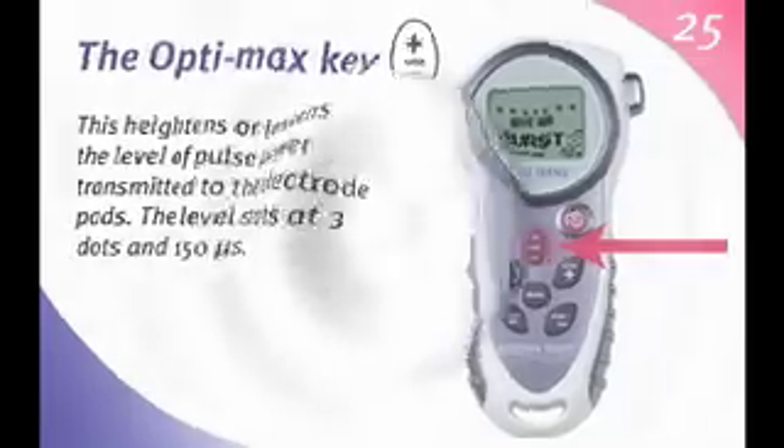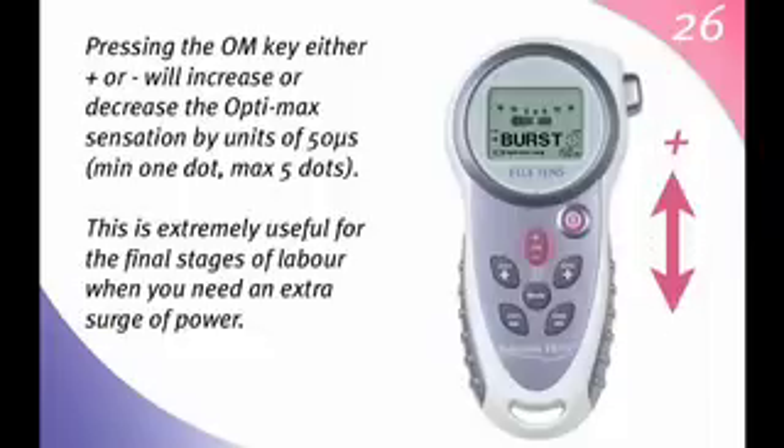The OptiMax key heightens or lessens the level of pulse power transmitted to the electrode pads. The level starts at 3 dots and 150 microseconds. Pressing the OM key either up or down will increase or decrease the OptiMax sensation by units of 50 microseconds. Minimum of 1 dot, maximum of 5 dots.